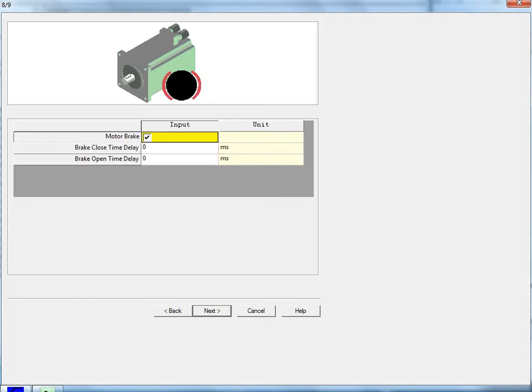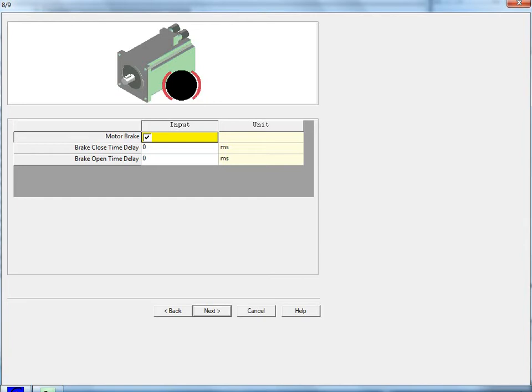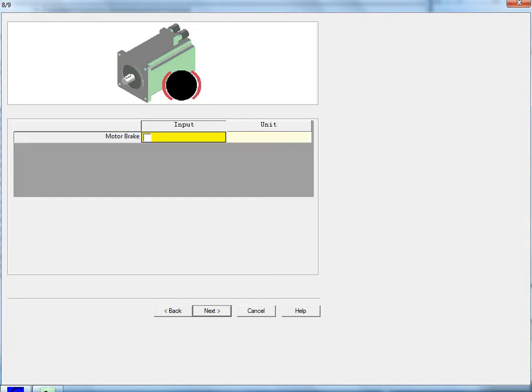Step 8 is used to set if the motor has a fail-safe brake or not. If it does, then you can set the set, which is the close, and the release, which is the open time delays. My motor doesn't have one, so I'm going to leave this unchecked. Note that the maximum current draw out of the brake output on the X3 connector is 1.6 amps. If your motor's brake's current draw is higher, then you'll need to run the brake output to a relay.